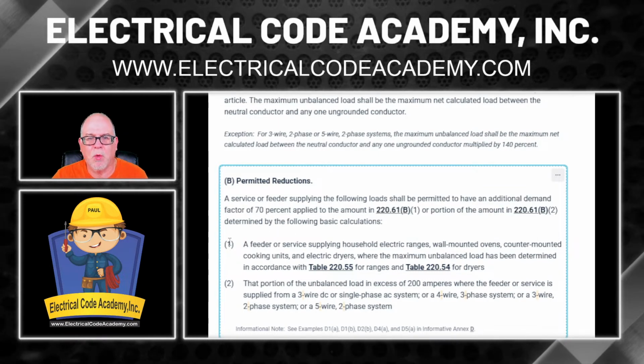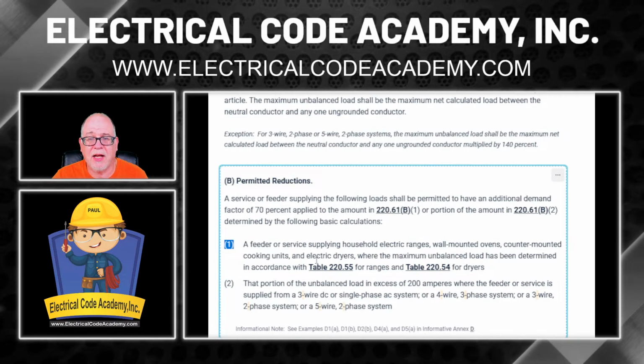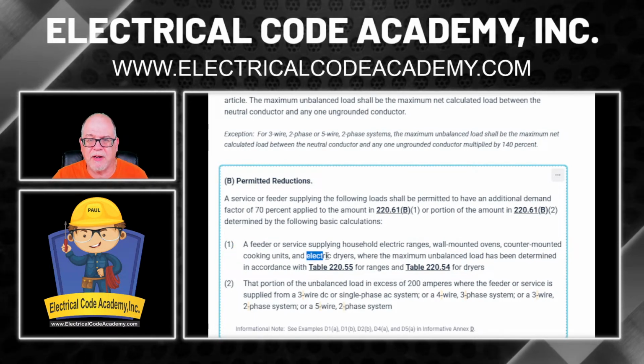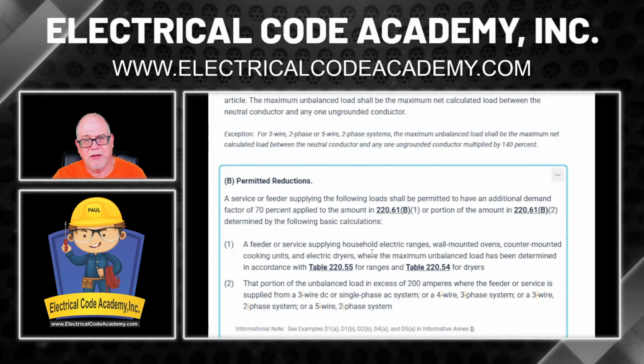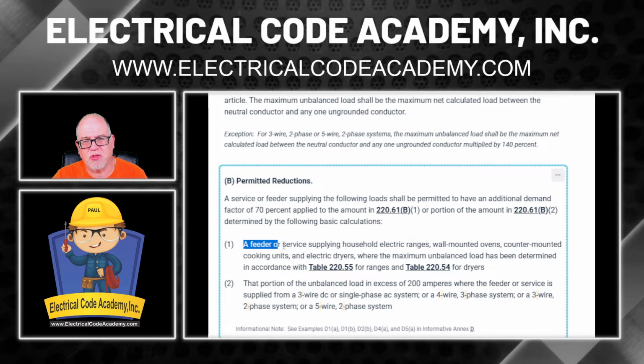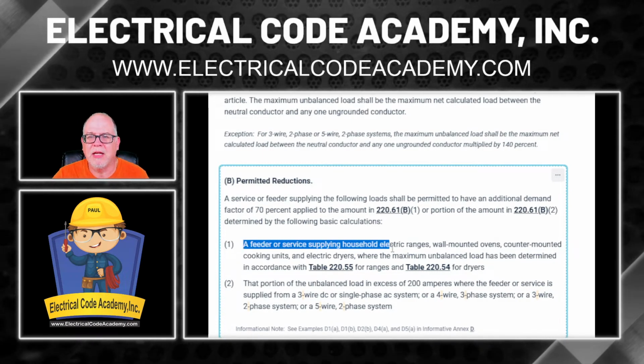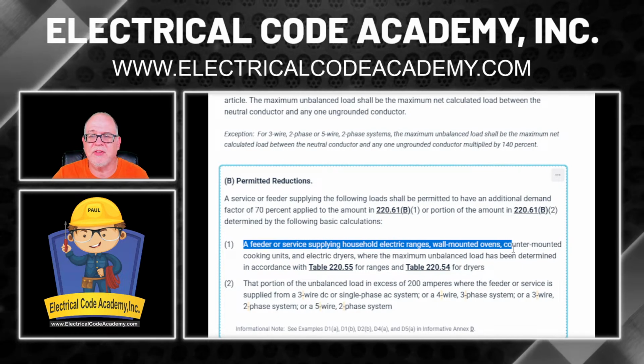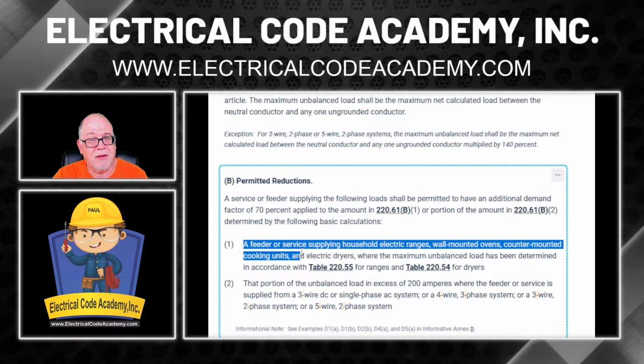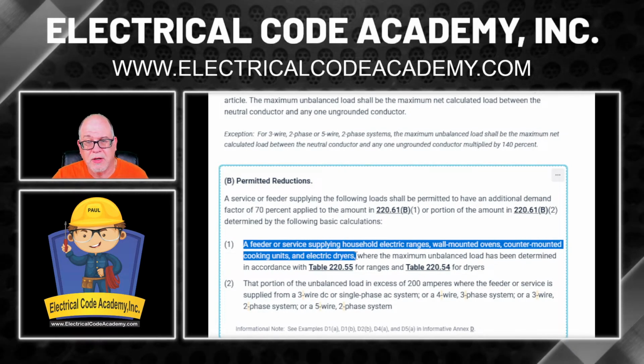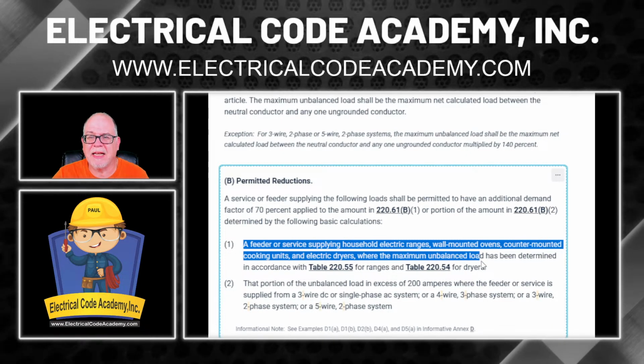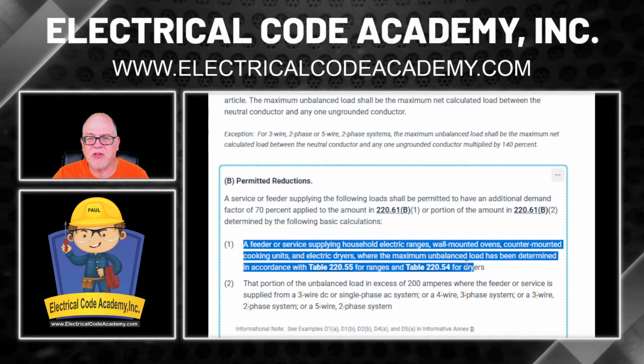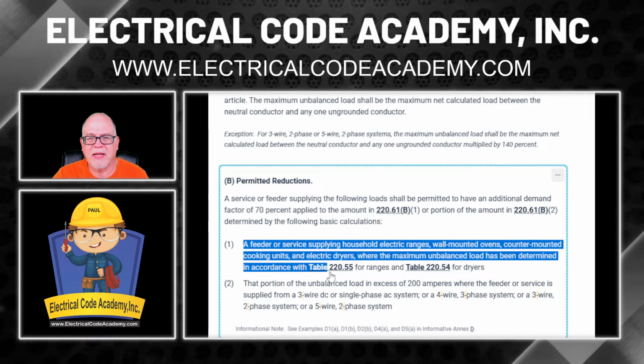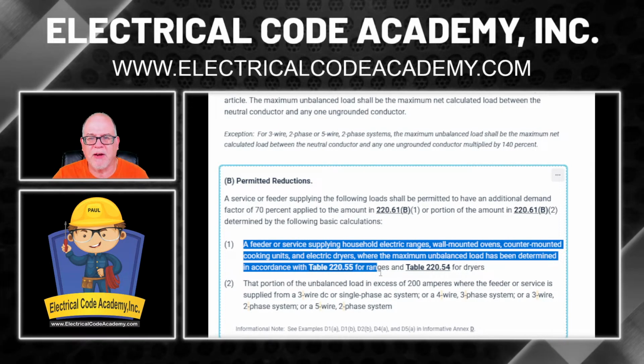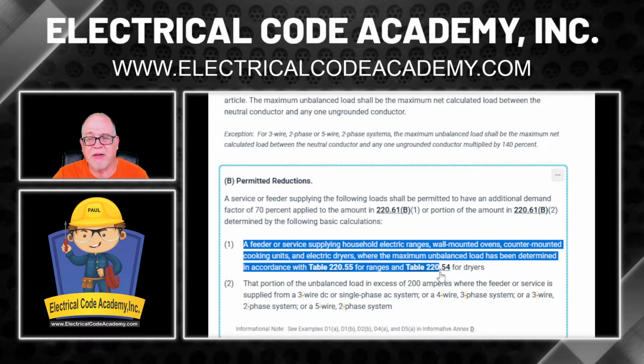All right. Well, we're going to be doing B1 because, as you'll notice right here, electric dryers are in here. So it says a feeder or service supplying household electric ranges, wall-mounted ovens, counter-mounted cooking units, and electric dryers where the maximum unbalanced load has been determined in accordance with Table 220.55 for ranges and Table 220.54 for dryers.